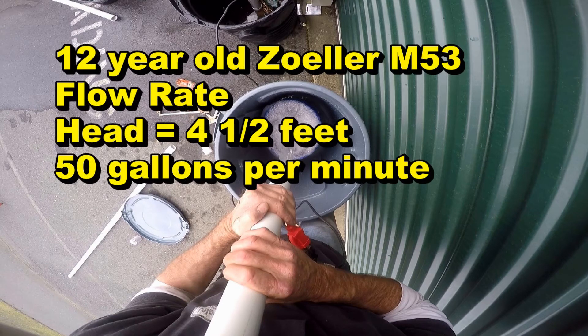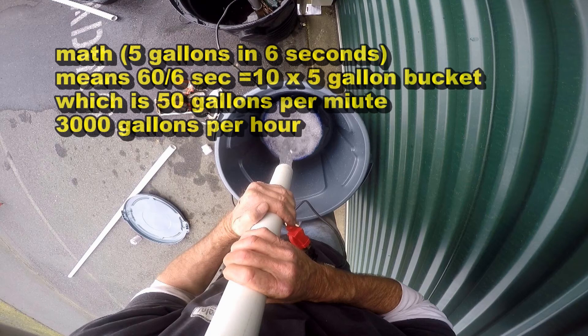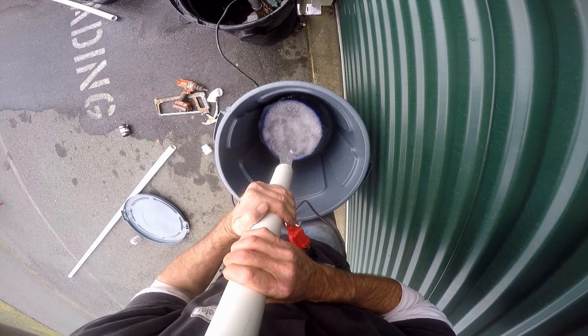The 12-year-old Zoeller M53 flow rate with a head of four and a half feet is 50 gallons a minute. Five gallons in six seconds means 60 divided by six seconds equals 10 times five-gallon buckets, which is 50 gallons per minute, or 3,000 gallons per hour.